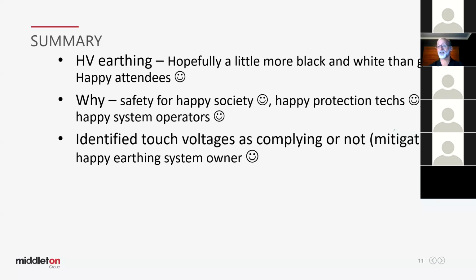We have happy protection techs, the protection's working, and we've got happy system operators that don't have any frequency or voltage excursions that they can't control. We've also identified where we can find some touch voltages, and comparing them to that last bit of software, we can see whether the voltages we measured around the switchyard and further out on fences comply with the allowable of the standard. And if they're not complying, we can do some design work and some mitigation. So hopefully we've got some happy earth system owners at the end of this once it's deemed to be safe.